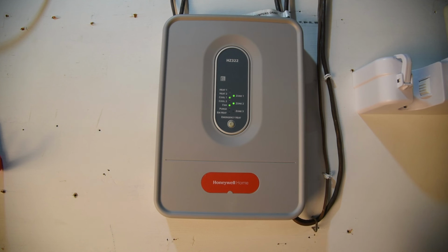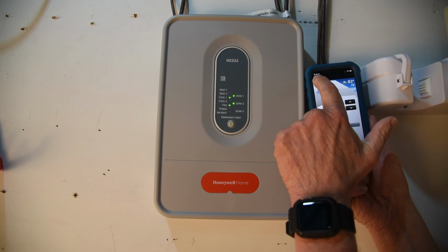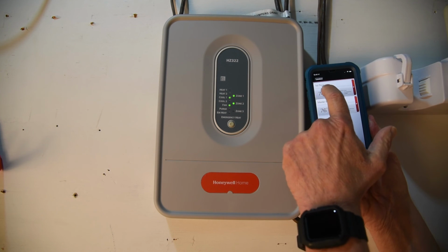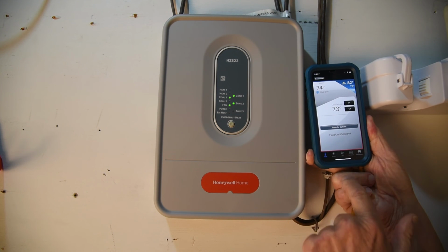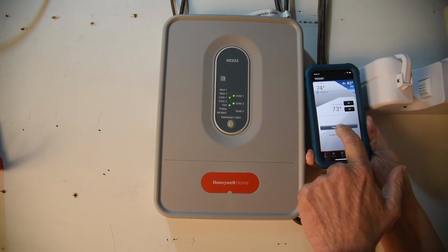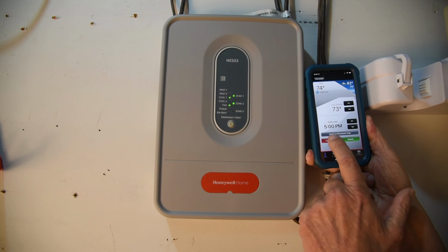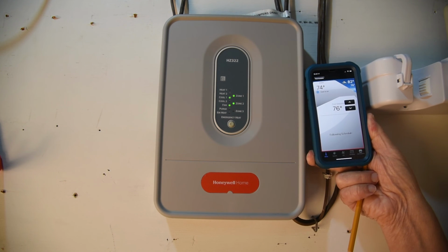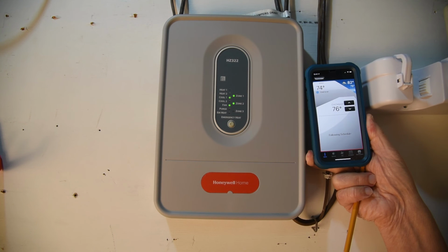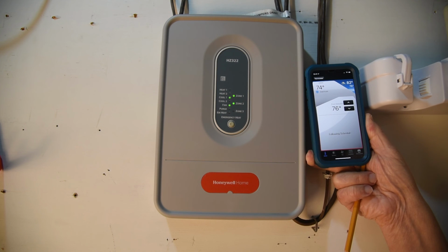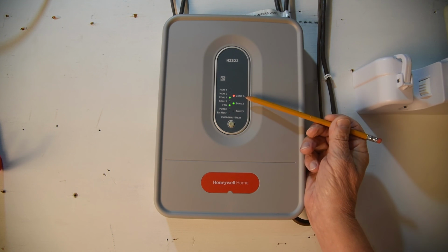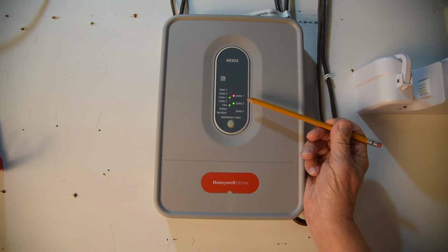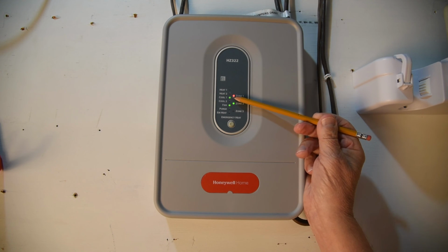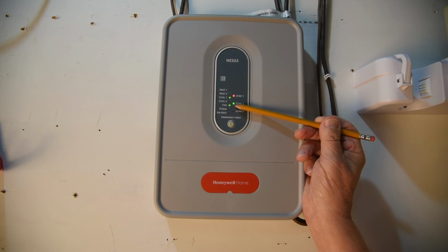If I go back to the thermostats, on the first floor I press options, and I want to cancel the last one. So now it's resetting, it will reset to 76. It takes a second before it resets. There it goes. Now, zone 1 is no longer calling for air conditioning. Zone 2 is calling for air conditioning, so you have cooling, zone 2, 1.